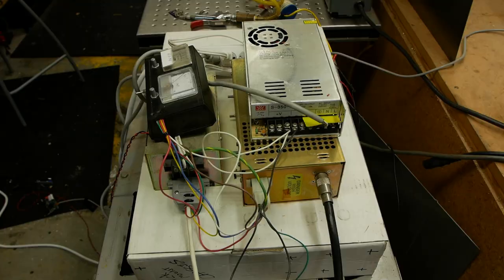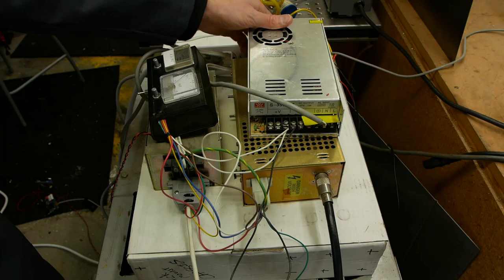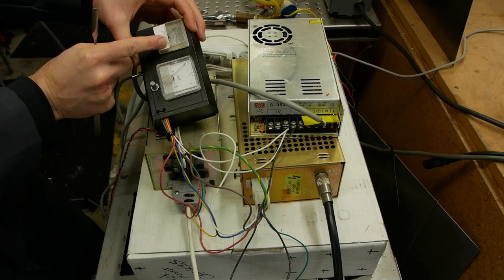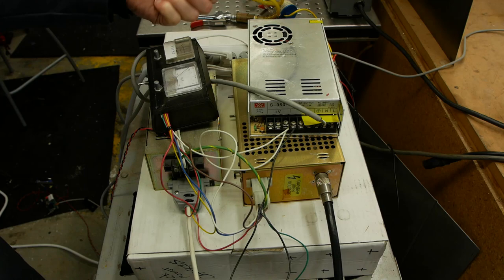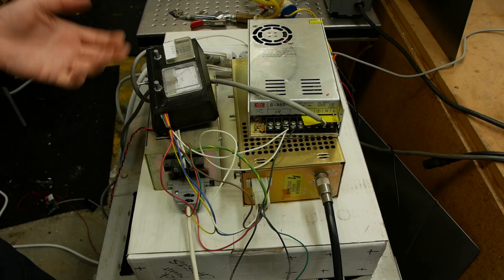Here's the power supply stack for the X-ray system. We've got a 27 volt supply feeding into the high voltage power supply. And that's controllable with this knob over here. It reads off in tens of kV. And this system operates almost independently. So remember I said you can turn the voltage up on an X-ray tube and nothing happens right away. You can keep that voltage on all the time, in fact, and that's okay.